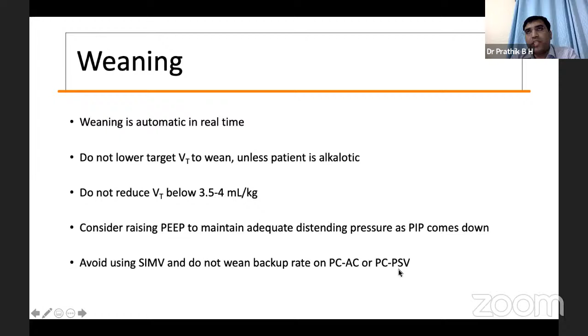You should not use SIMV, and do not wean the backup rate in pressure control and assist control or PSV. In SIMV, you should not use volume guarantee. The reason is that in SIMV, only the breaths which are triggered by the baby are volume guarantee. For the untriggered inflations, volume guarantee is not supported. Whereas in assist control and pressure support ventilation, every breath of the baby which is above the trigger level is supported. That is why we prefer assist control or pressure support ventilation when you give volume guarantee, not SIMV.